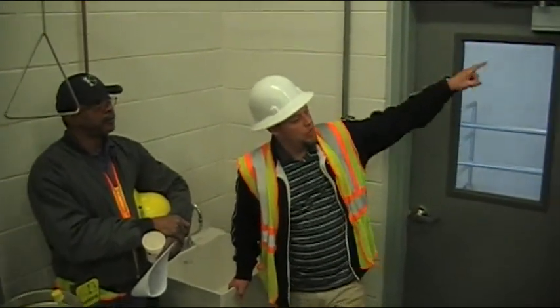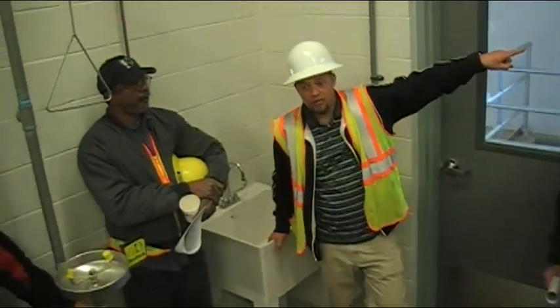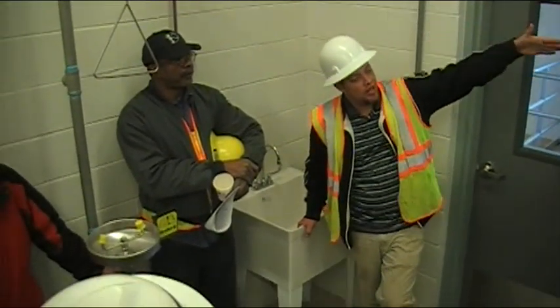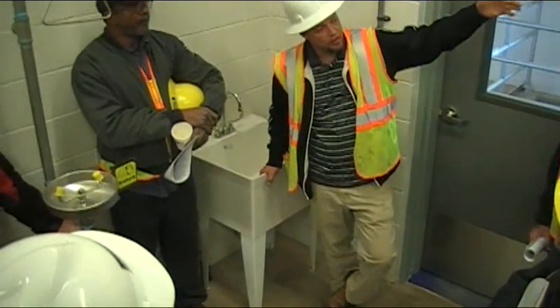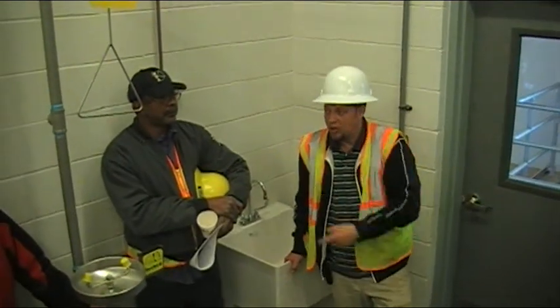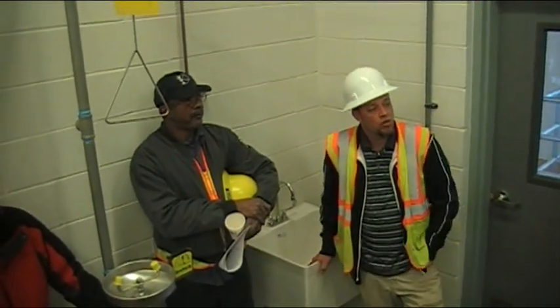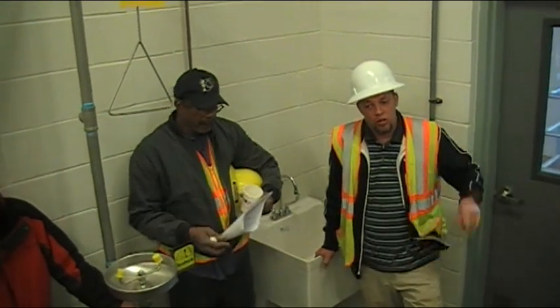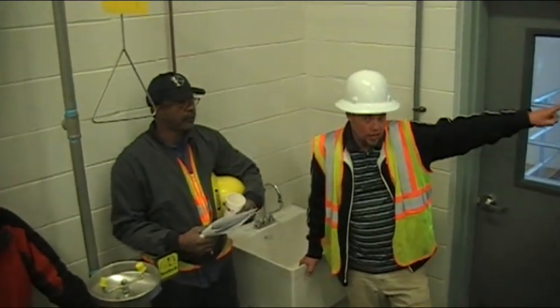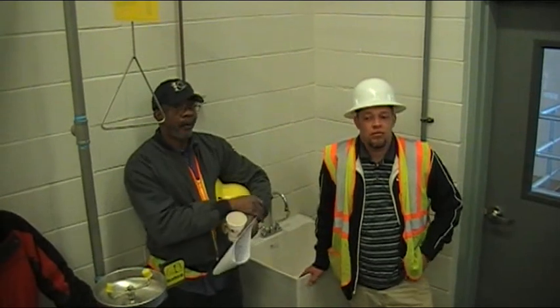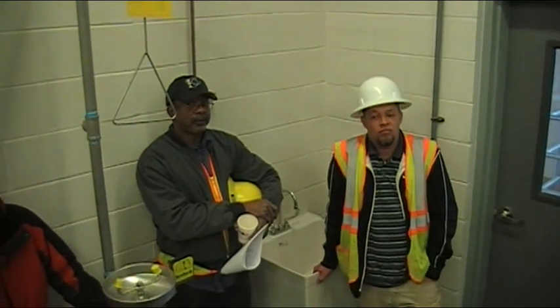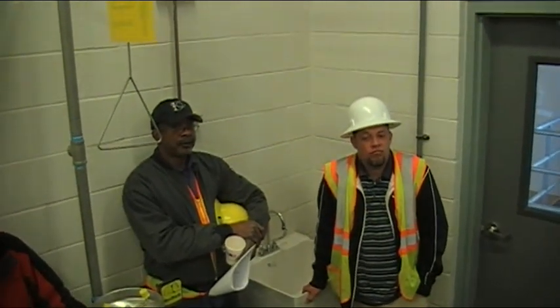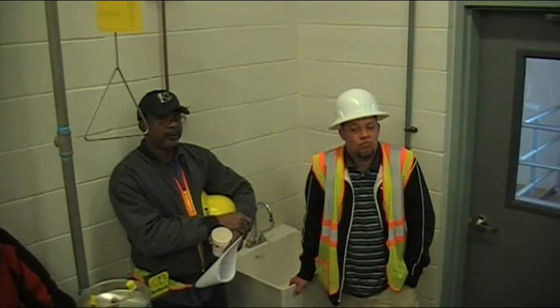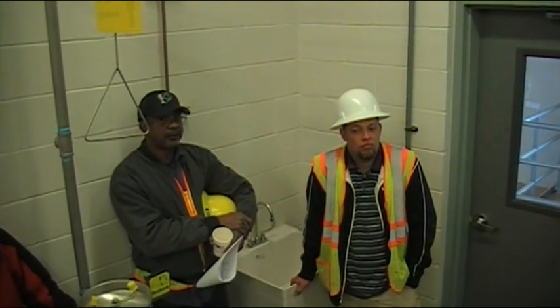In order, that SCADA PLC panel over here - if that contactor in there, any of those relays, if they're closed, that means this will restart. So the question you're asking depends on that. The question you want to ask SCADA is, if we have a power outage, when we power back up, are you going to tell it to start back up again, or do we have to go through something else?